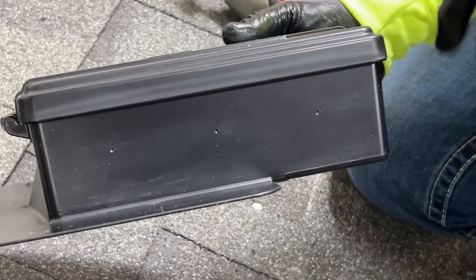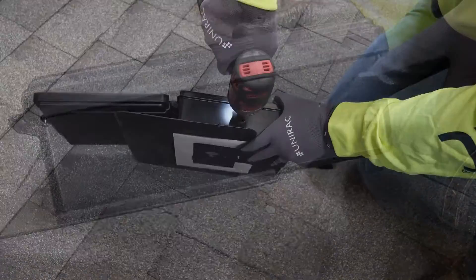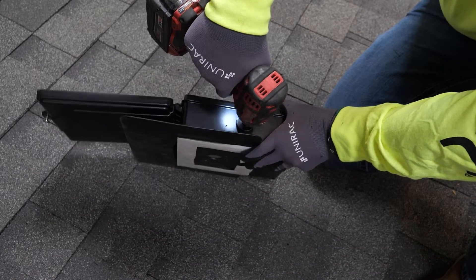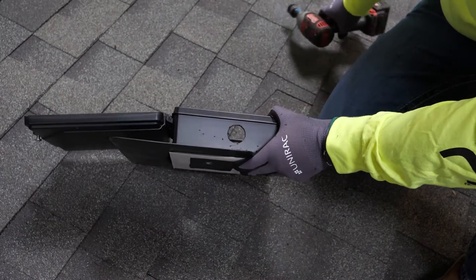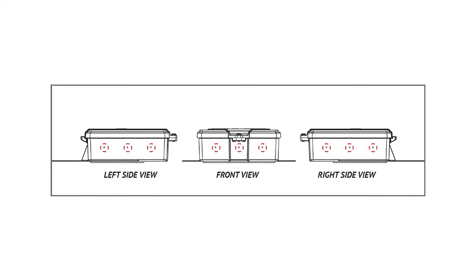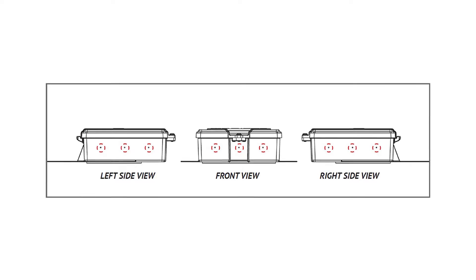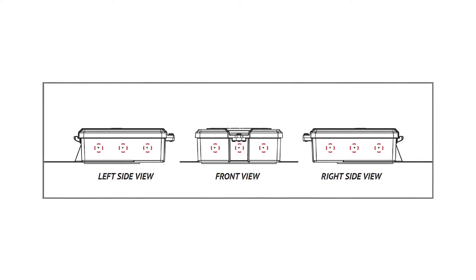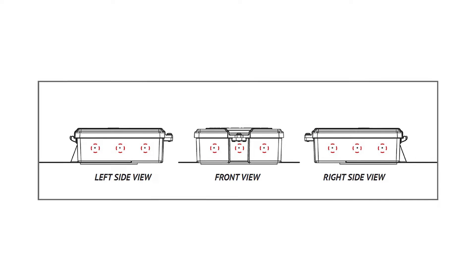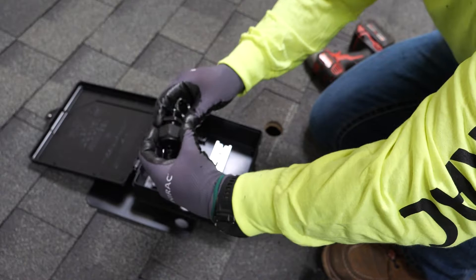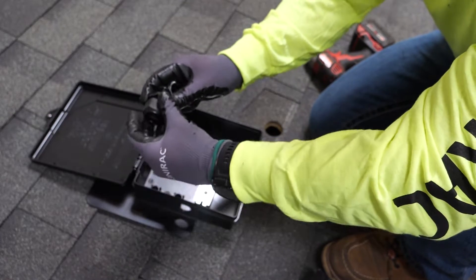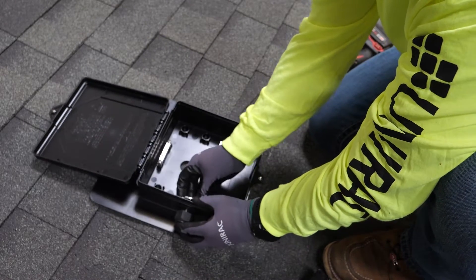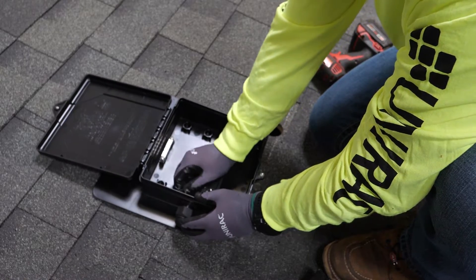Holes in the sides of the Solobox Comp that accommodate PV wires leading into the enclosure can now be drilled. Be sure to only drill into the two side and bottom walls of the enclosure at the points indicated, never on the top wall, which faces the ridge of the roof. Holes on the walls of the enclosure can be up to 1 inch in diameter, and a strain relief can be installed into these holes.